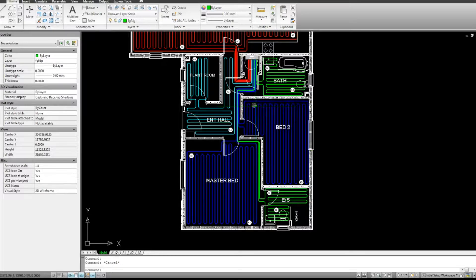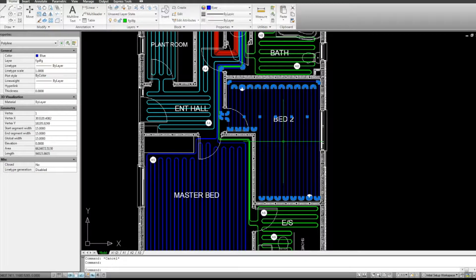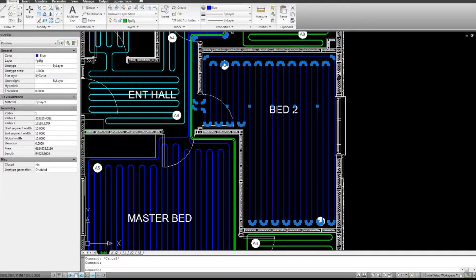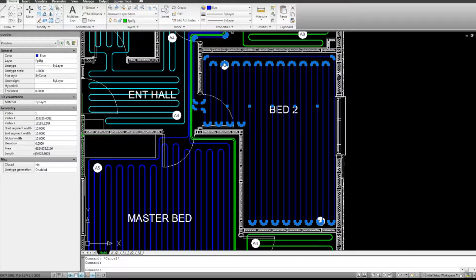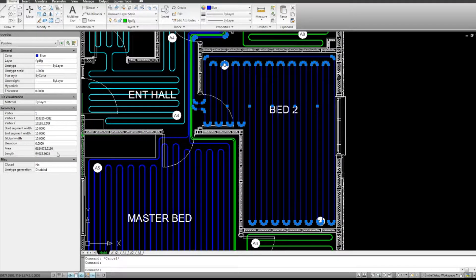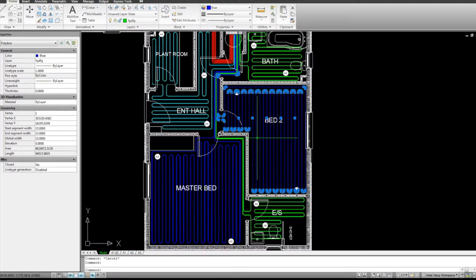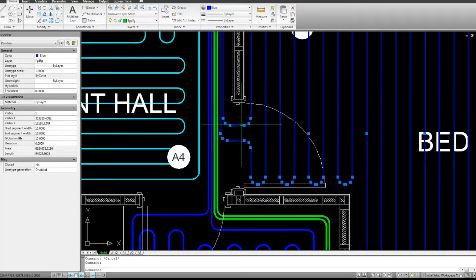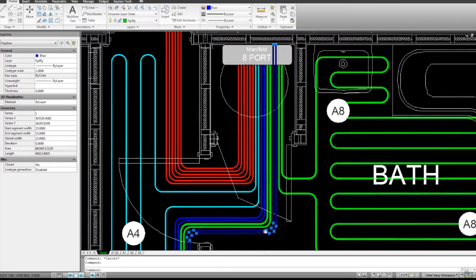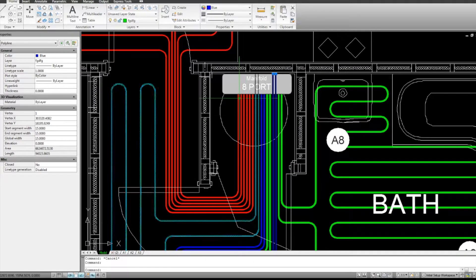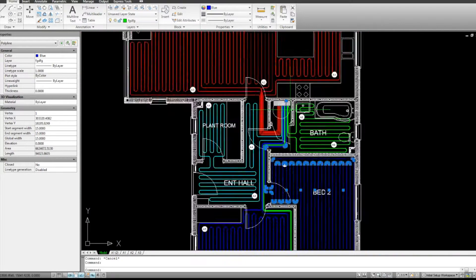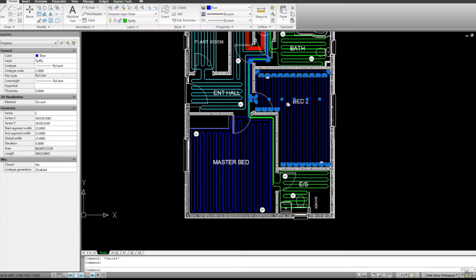Now we've got down here a separate bedroom. Again, the pipe length on this one, if I come over here, you can see is 94 metres. So we don't need a second circuit, so one is fine. That's including the distance to get back to the manifold. I'm going to be talking about manifolds in a future video, so please stay tuned for that.